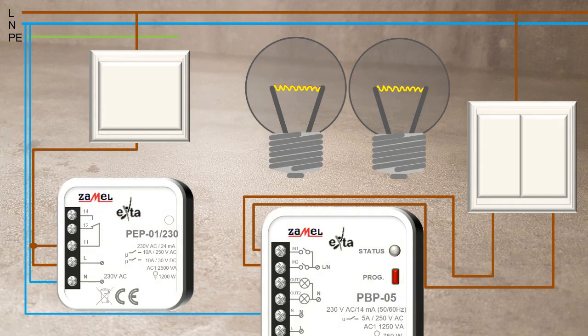To ensure interruption of the power supply to the PBP05 bistable relay by the PEP01230 electromagnetic relay, provide the phase potential to both terminal 11 of the PEP01 relay and the L terminal as well. After providing the phase signal, the PEP01 device will be activated. The relay will remove power from terminal 12 and provide it to terminal 14.